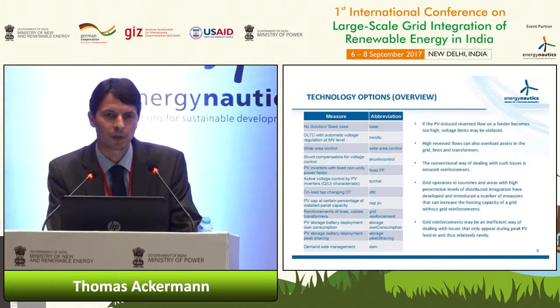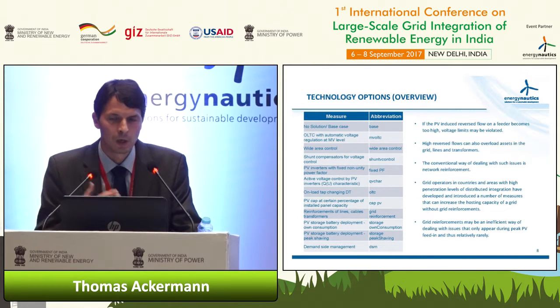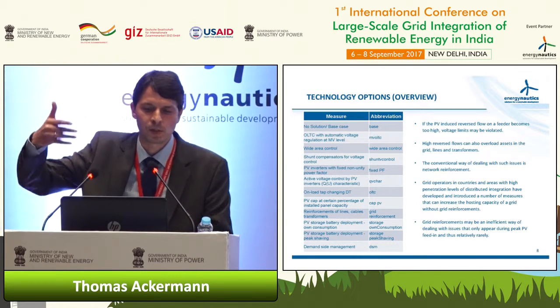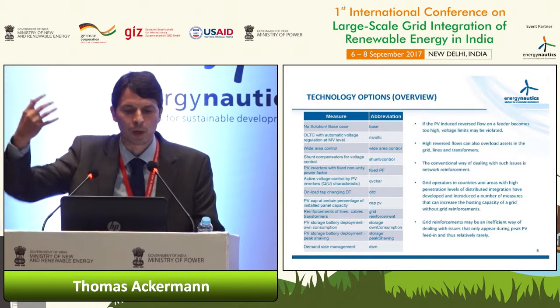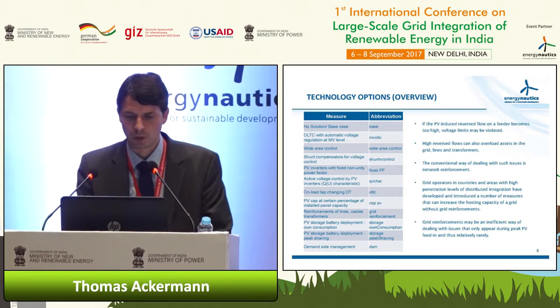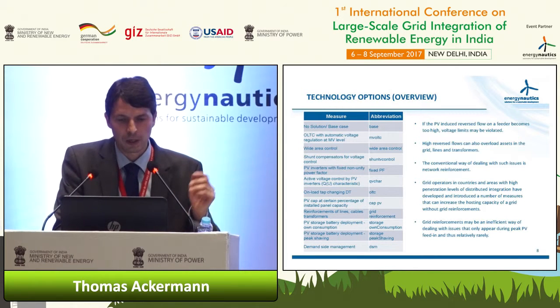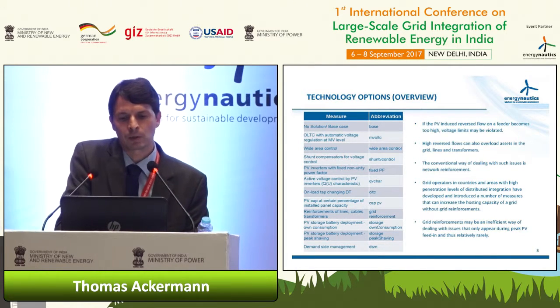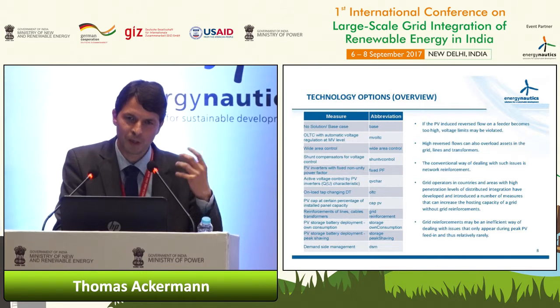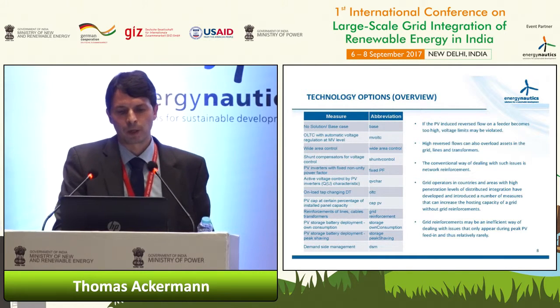We looked into using reactive power: a fixed power factor so that when the PV system is feeding in, it consumes reactive power to pull the voltage down to a certain level, or more advanced, using a QV characteristic, making use of reactive power depending on the voltage itself.